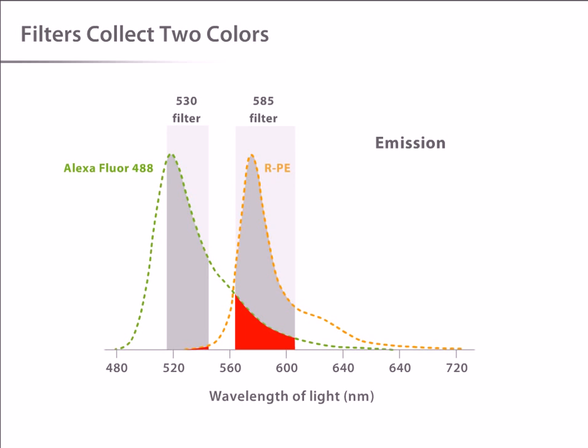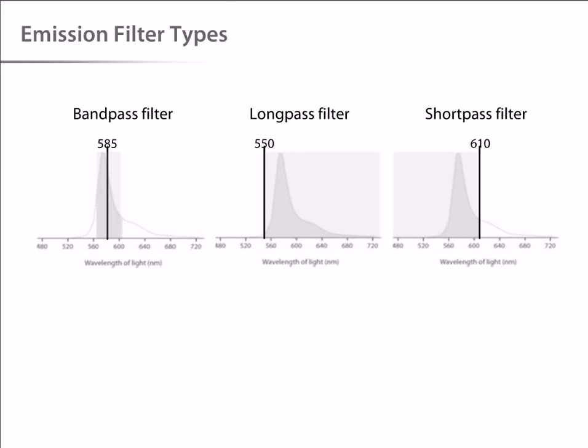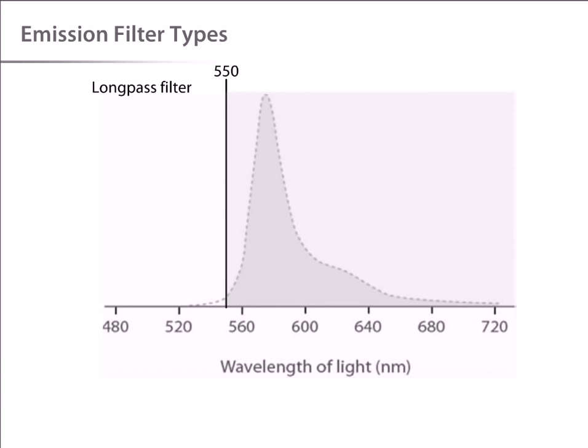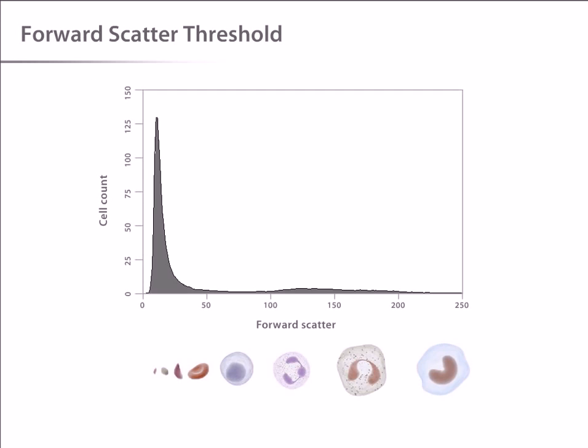Let's take a moment to talk about filter nomenclature. Filters are normally defined by one of two parameters, either the center point for a bandpass filter or the cutoff point for a long or short pass filter. This is a typical bandpass filter specific for R-PE. It has a center point of 585 nanometers and a width of 42 nanometers, so this filter optimally passes light in the wavelength range of 564 to 606 nanometers, which corresponds to the emission peak of R-PE. Other filters used to resolve this peak include a 550 nanometer long pass filter and a 610 nanometer short pass filter.